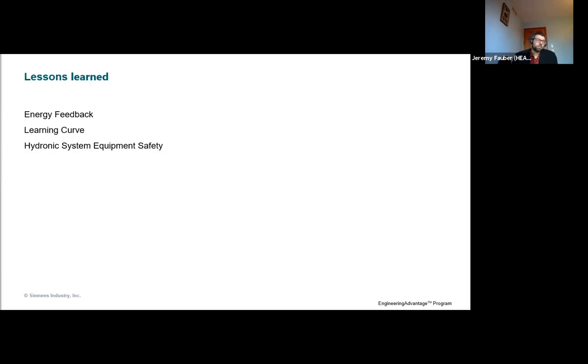Want to touch a little bit on lessons learned. I'm going to say these are anecdotal, just because it's really spot cases of talking with individuals. The buildings that were looked at were generally occupied with fewer people, and it was a stated goal to be at 50% of their typical occupancy. What they found is they operated with lower than normal utility bills in the summer, but higher than normal utility bills in the winter.